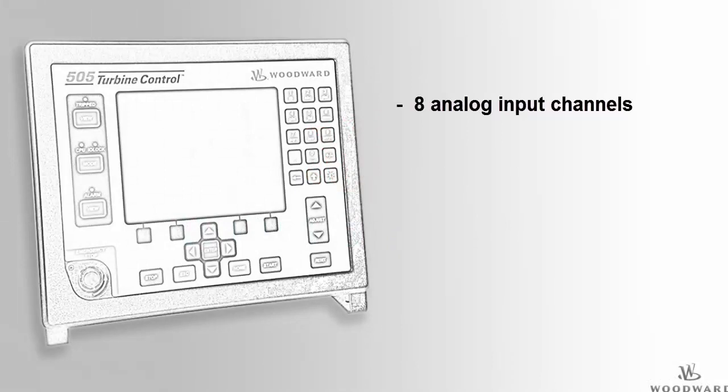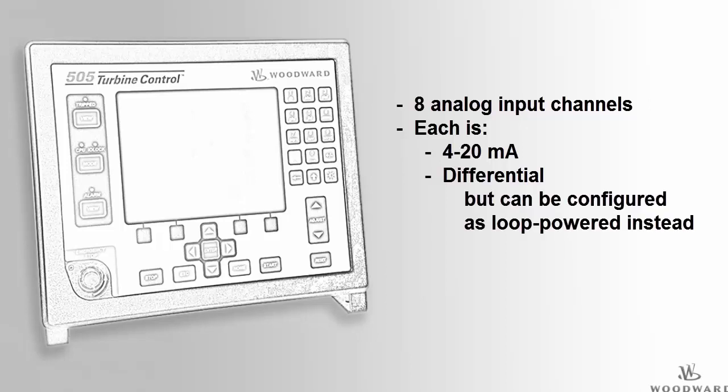The 505 has 8 four to twenty milliamp analog input channels. Each channel is differential but can be configured to be loop powered.